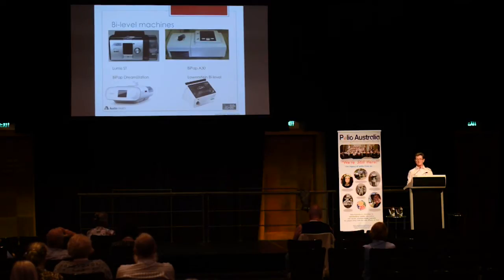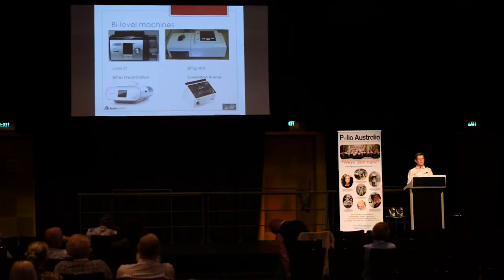All of these have the capacity to ventilate someone up to a set pressure decided by the clinician, and with breath rate and other variables you can again customise the ventilation, whereas in the earlier models you could select a pressure and a rate and that was all you could do. You couldn't adjust the flow patterns to make it more comfortable for the individual. You can do that on all of these machines, and the 2 machines on the right hand side both have internal batteries. So again, someone who's using a bilevel device and normally only uses it at night, wants to go out and they're a bit concerned about getting fatigued through the day, they can take their machine with them, leave it in the car, and if they get tired, they can go and get their machine and just sit down and use it for a little while and help catch their breath.